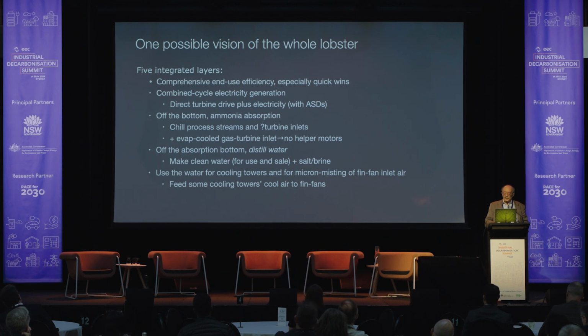Evaporatively cool the gas turbine inlets as well, eliminating their helper motors. Then off the bottom of the ammonia chillers, distill water for use and sale, along with salt and brine byproducts. Use the sweet water in very efficient cooling towers and to micromist inlet air to the efficient fin fans, and maybe cascade some cooling tower exhaust air to the fin fans, and probably more integrations after that. So a key insight is when you're thinking about integrating heat flows, think also about how to integrate and create new value from water flows, especially in a desert.